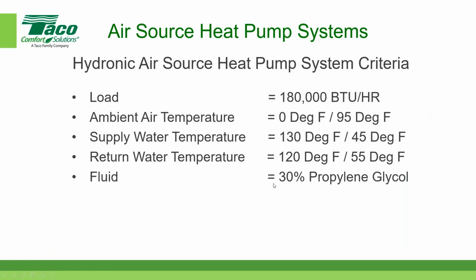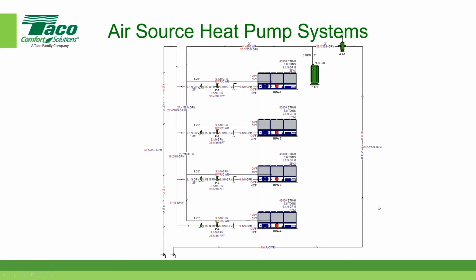Okay, and in our case, we're going to do 30% propylene glycol, and our flow is around 36.5 gallons per minute. And if you want to do the arithmetic out, if you take 180,000 BTUs per hour divided by 500 divided by 10, it comes out to 36. When I did the actual calculation, accounting for propylene glycol, it came out to 36.5. And this is what the diagram looks like. So I'm going to provide, and again, what we said at the beginning of this discussion is Brett's going to go through this design software in detail. So I'm just showing you what I did.